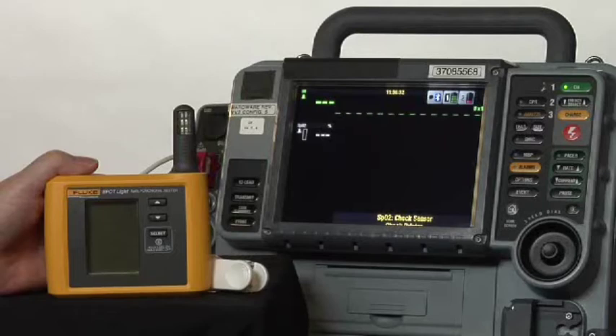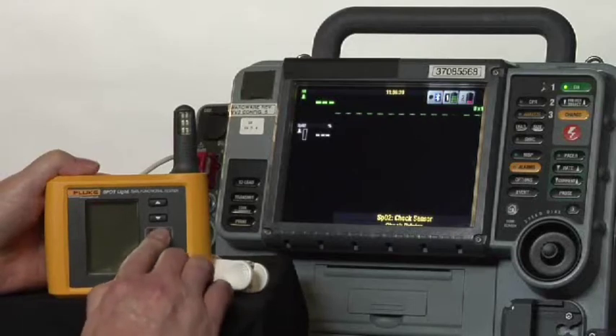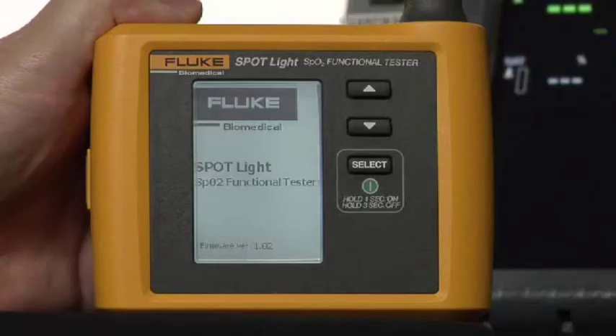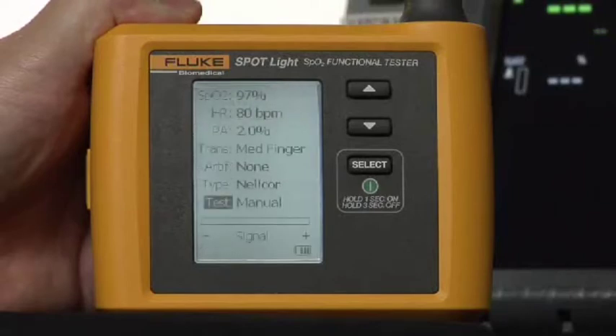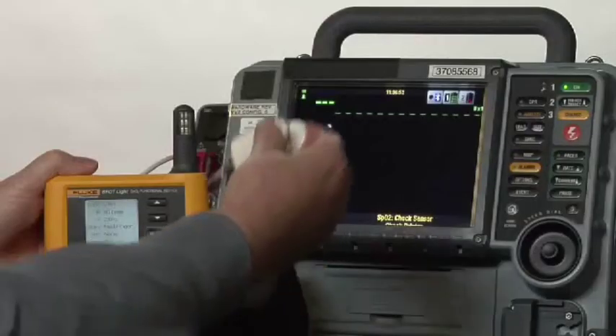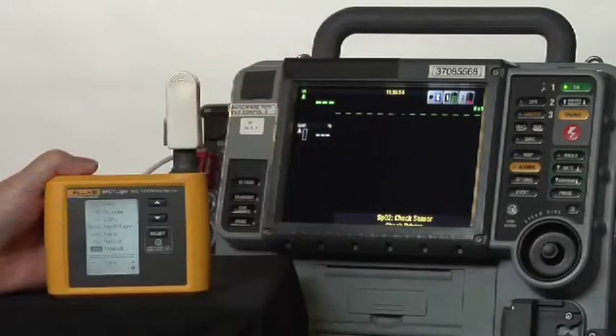In this case, we find the device turned on. It's a defibrillator. We will turn on our Spotlight SpO2 functional tester, wait for it to go through its self-check, and we will then connect the oximeter sensor from the medical device, and we'll watch this bar down at the bottom. It's called the signal strength bar, and you can see that it has a good signal, and you will begin to see the display on the screen of the defibrillator.